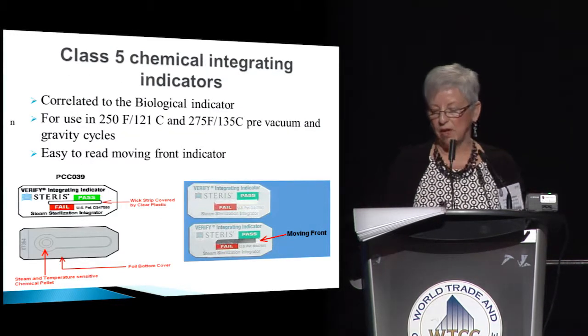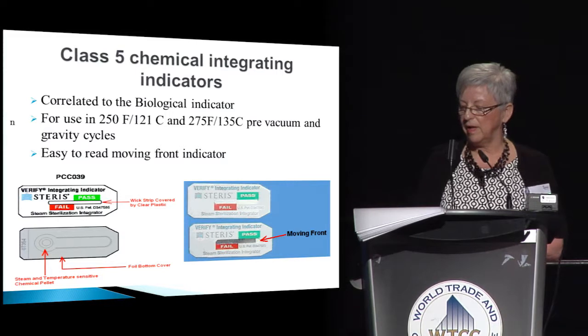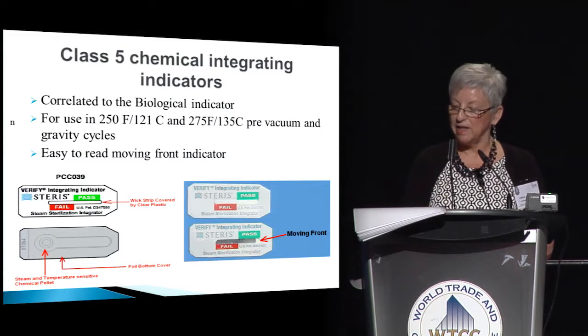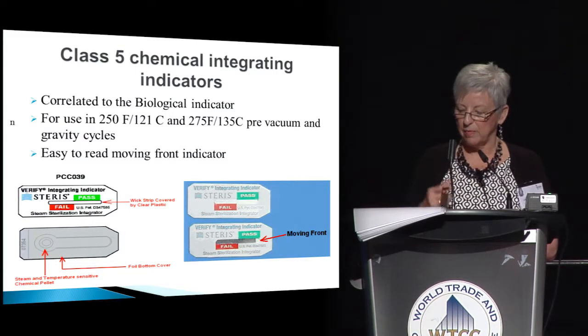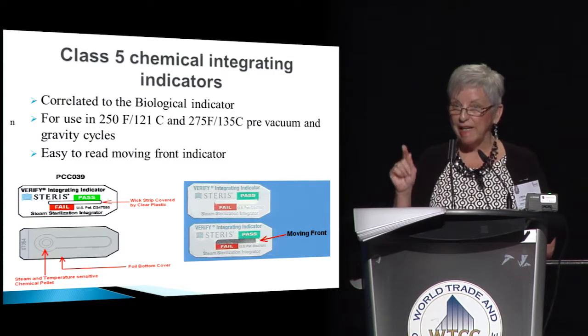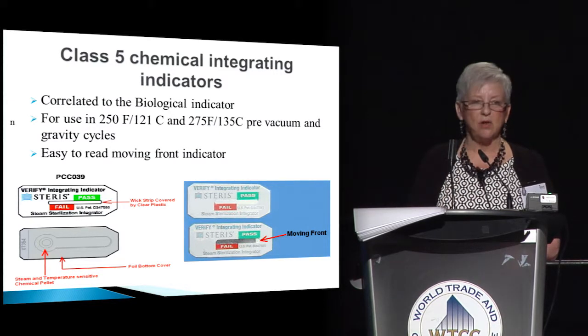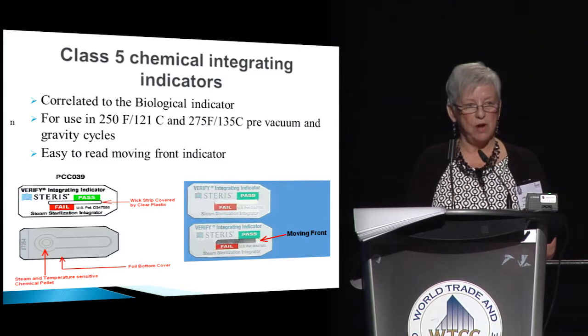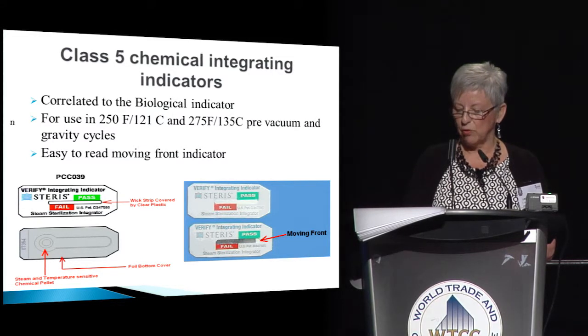So Class 5 chemical integrating indicators, and this is going to really mess me up, but a Class 5 integrating indicator is correlated to the biological. It's for use in different temperatures and times. It's for 250 Fahrenheit to 275 Fahrenheit in pre-vacuum and gravity sterilizers. It's easy to read. It's got a front indicator that moves.